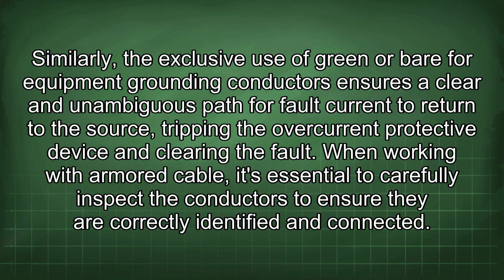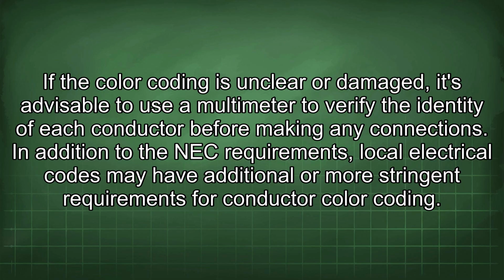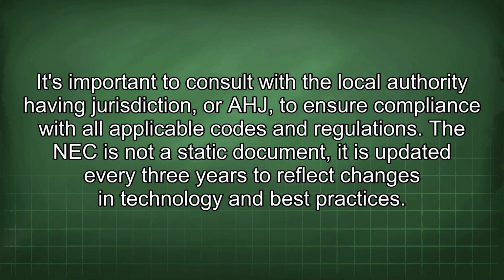When working with armored cable, it's essential to carefully inspect the conductors to ensure they are correctly identified and connected. If the color coding is unclear or damaged, it's advisable to use a multimeter to verify the identity of each conductor before making any connections. In addition to the NEC requirements, local electrical codes may have additional or more stringent requirements for conductor color coding.